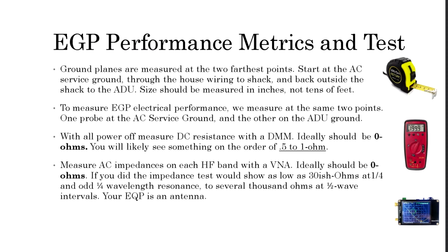Same with electrical performance. We measure at the same two furthest points. We put our probes on the AC service ground and the other end on the ADU ground. You can turn all the power off and measure the DC resistance. With that long circuit, you're going to be measuring half an ohm to 1 ohm. You should be seeing 0 ohms. Same with AC impedance, if you were to measure it. You could do it with a VNA, and ideally, again, it should be 0 ohms. But it's not. I can tell you, it's going to be as low as 30 ohms at quarter wave and odd quarter wave resonant frequencies, up to several thousand ohms at half wave intervals. So essentially, your equipment ground plane is an antenna.